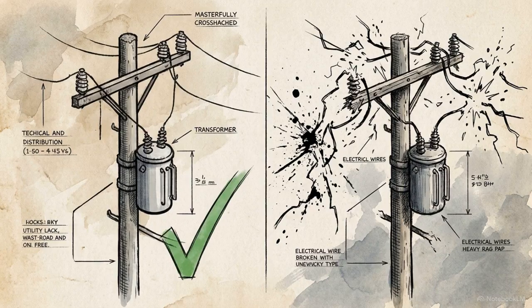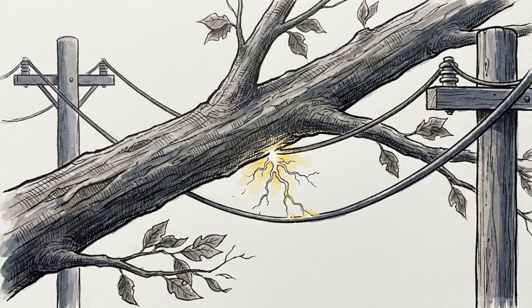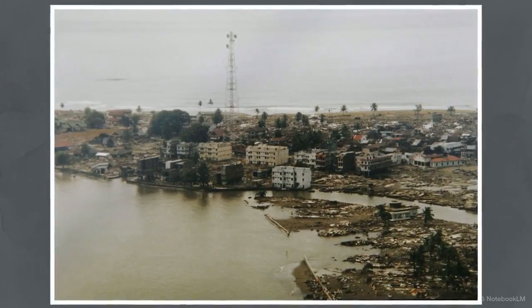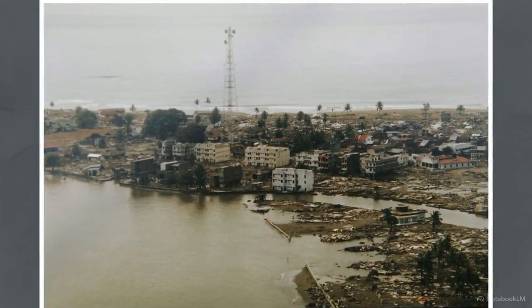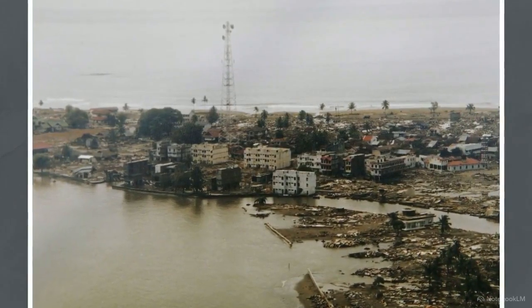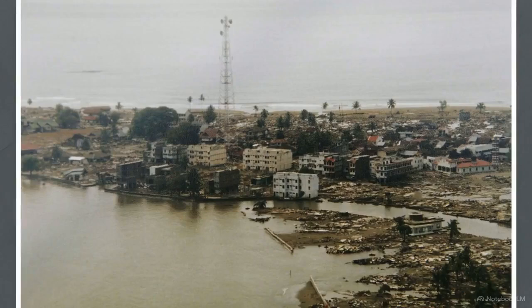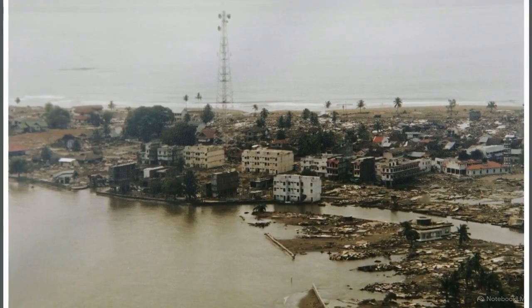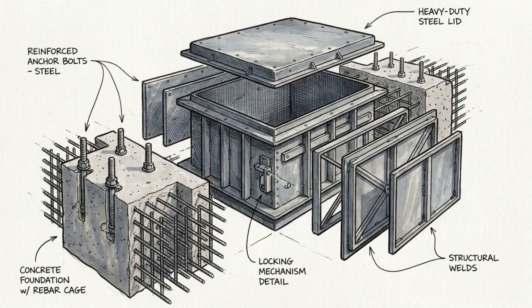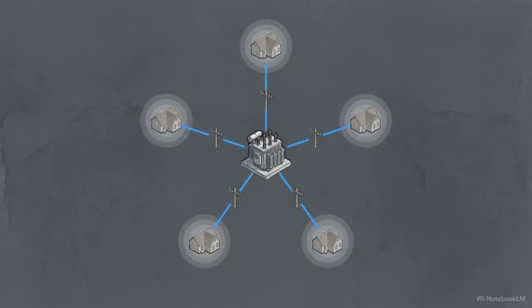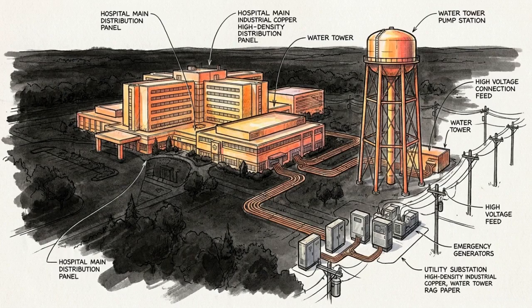But these metrics track high-probability, low-impact events, things like a tree falling on a wire or an animal shorting a transformer. In the aftermath of a major earthquake or tsunami, routine reliability metrics are irrelevant. When coastal infrastructure is wiped away, the numbers stop mattering. This massive scale of destruction requires resilience. We define this as the grid's ability to survive the initial shock, operate autonomously, and sustain critical loads when the main grid is gone.